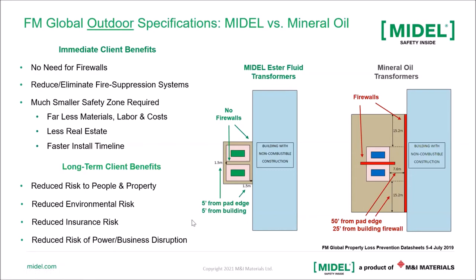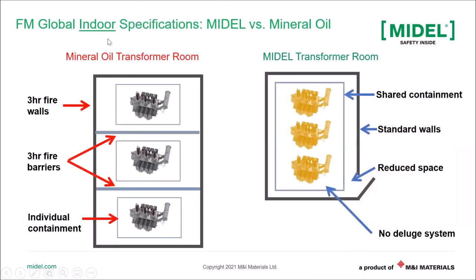Now, when we think of indoor guidelines, here is what you see for a mineral oil filled transformer. There would be a 3-hour firewall for the building around the transformers. And if you have three transformers, each transformer would have to have individual containment as well as a 3-hour fire barrier between them. When you think of a MIDEL filled transformer, it can share a common containment. It can just be a standard room and there would be a reduction in space as well. And another key point here is the deluge system. There would be no requirement to have a deluge system over the transformer.